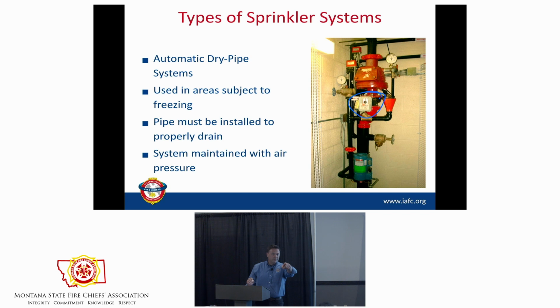Then I do what? Open the main drain. That's that bad boy right there. Right? And we should start to get that water out. Now, we're not going to put that system back in service. That's a qualified contractor, and that's really going to be our stuff. But when we have tripped dry systems, we need to figure out why it tripped. So this thing right here is a compressor. If you touch that and it's hotter than heck, right?